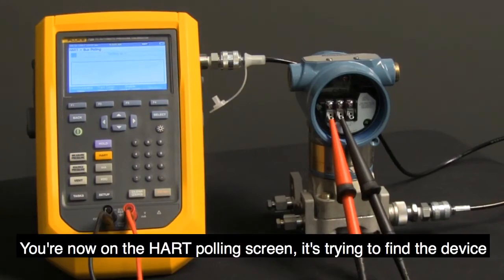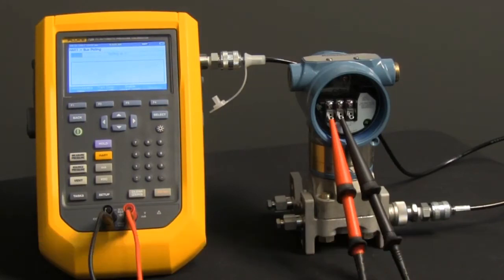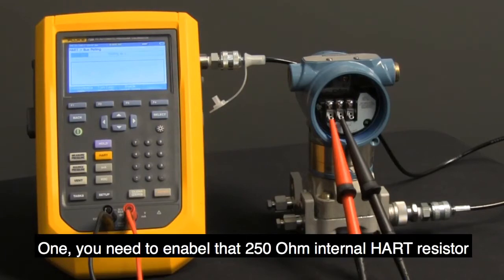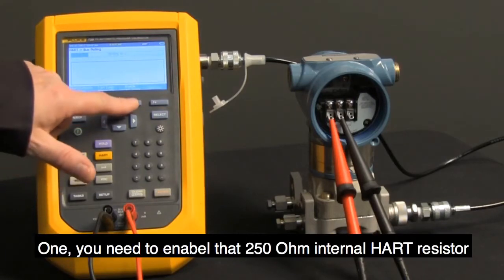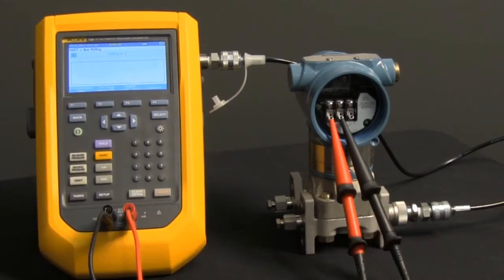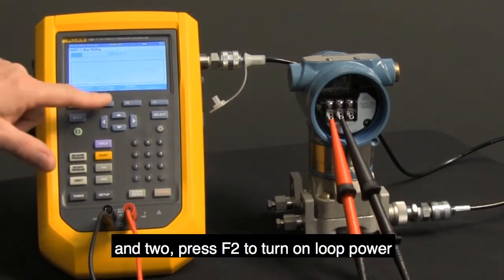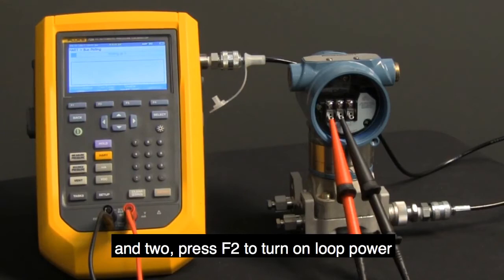You're now on the HART polling screen. It's trying to find the device. Two things you need to do: one, enable that 250 ohm internal HART resistor, and two, press F2 to turn on loop power.